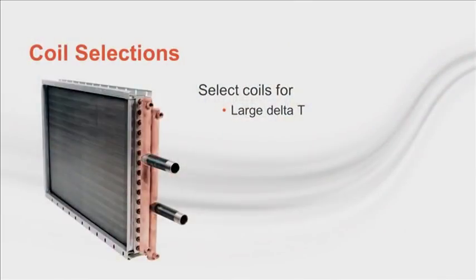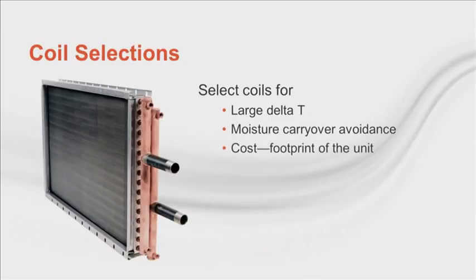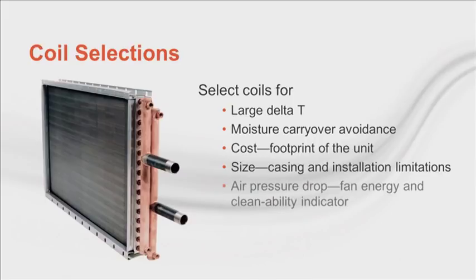For constant flow systems, it's critical that coils are optimally selected, since the flow cannot be used as a variable to optimize energy consumption. Going with the lowest constant flow you can get means selecting coils for high DeltaT. Some coils are more capable of this than others, but in virtually all applications there is an option to improve DeltaT. Other considerations in coil selection include avoiding moisture carryover, cost, size, air pressure drop, and cleanability.